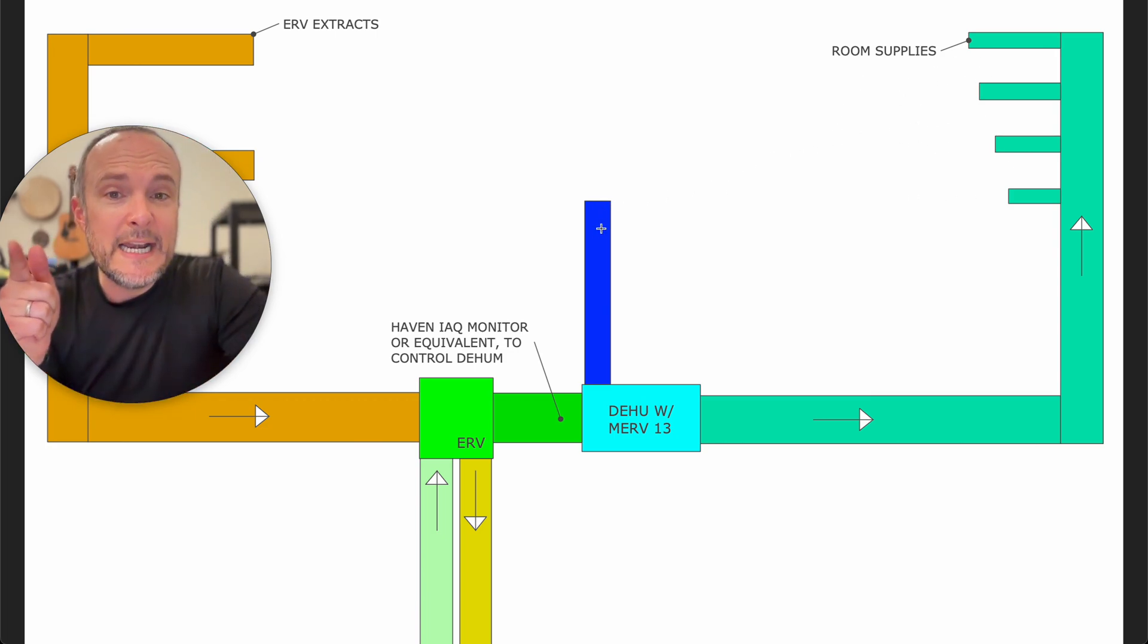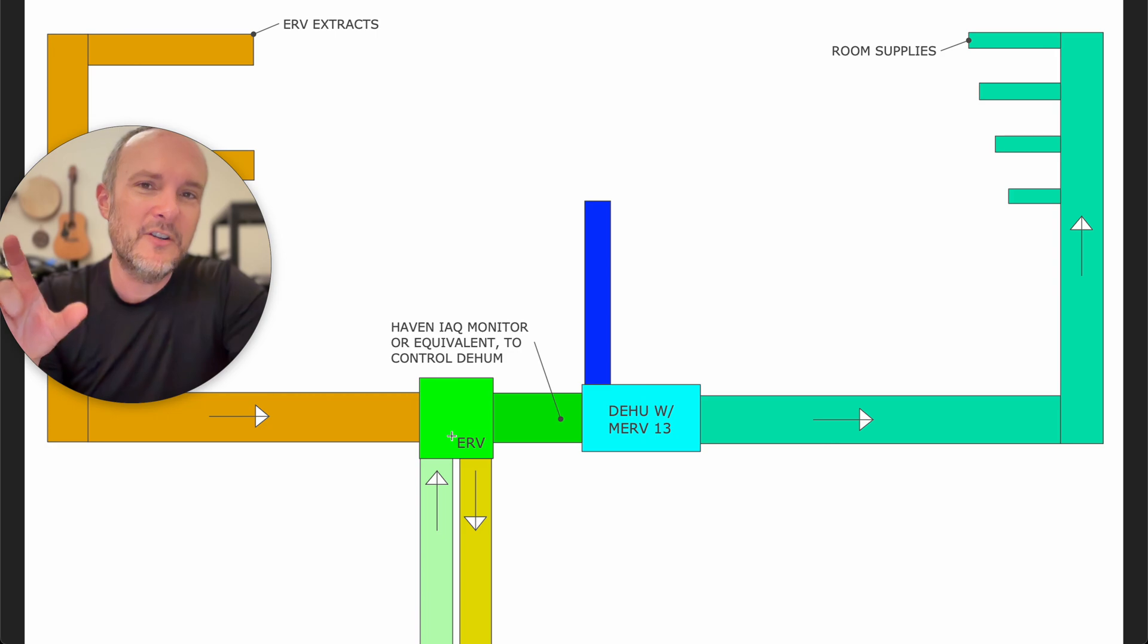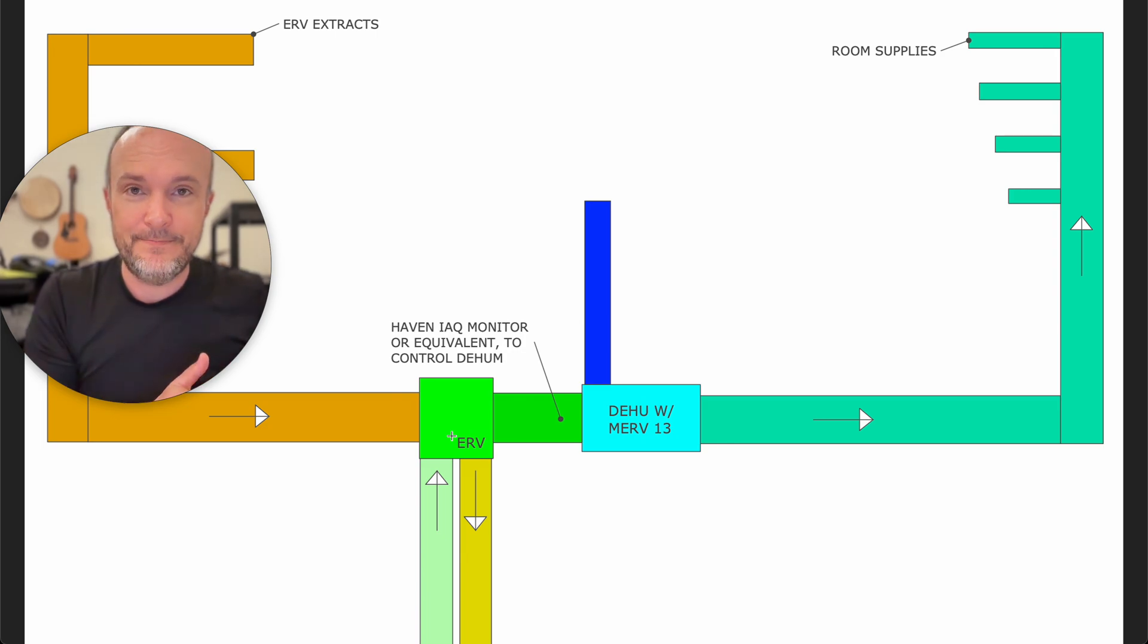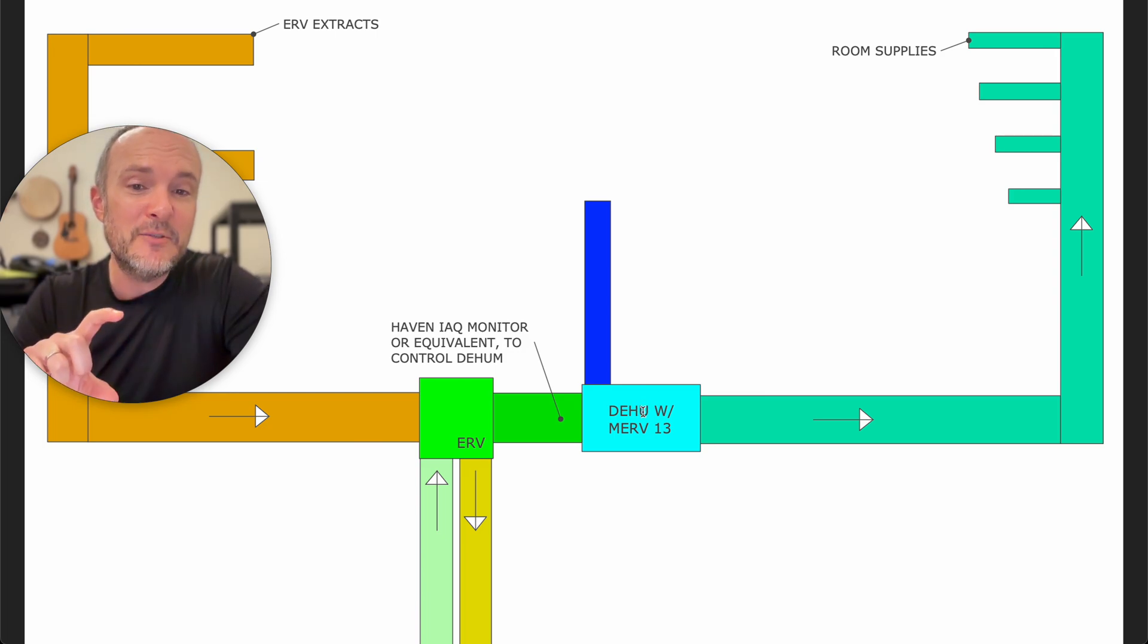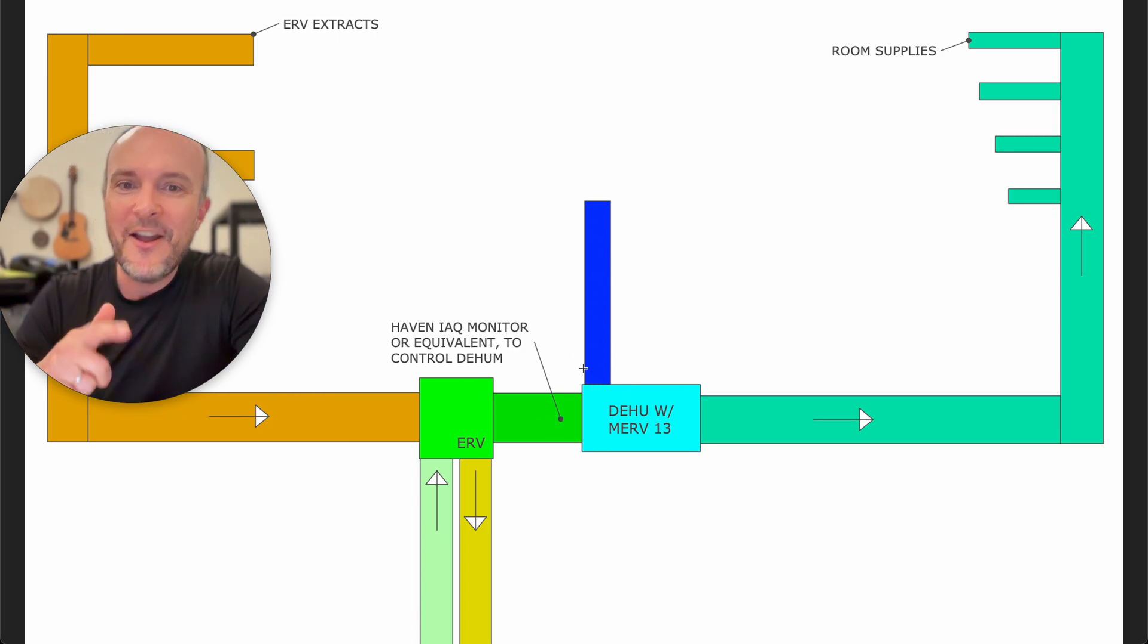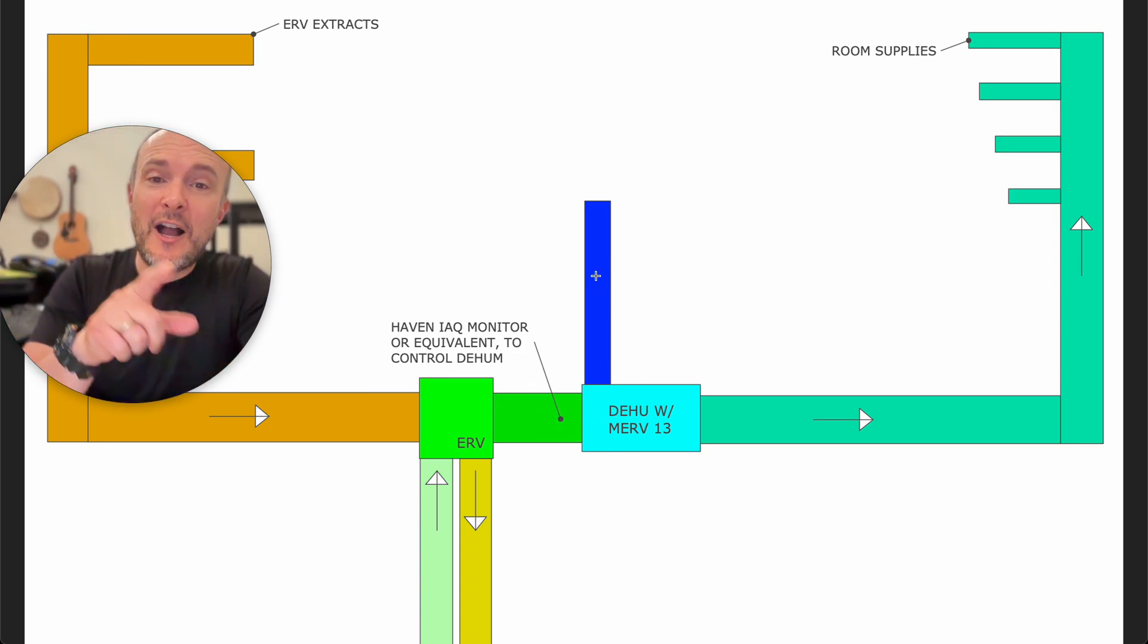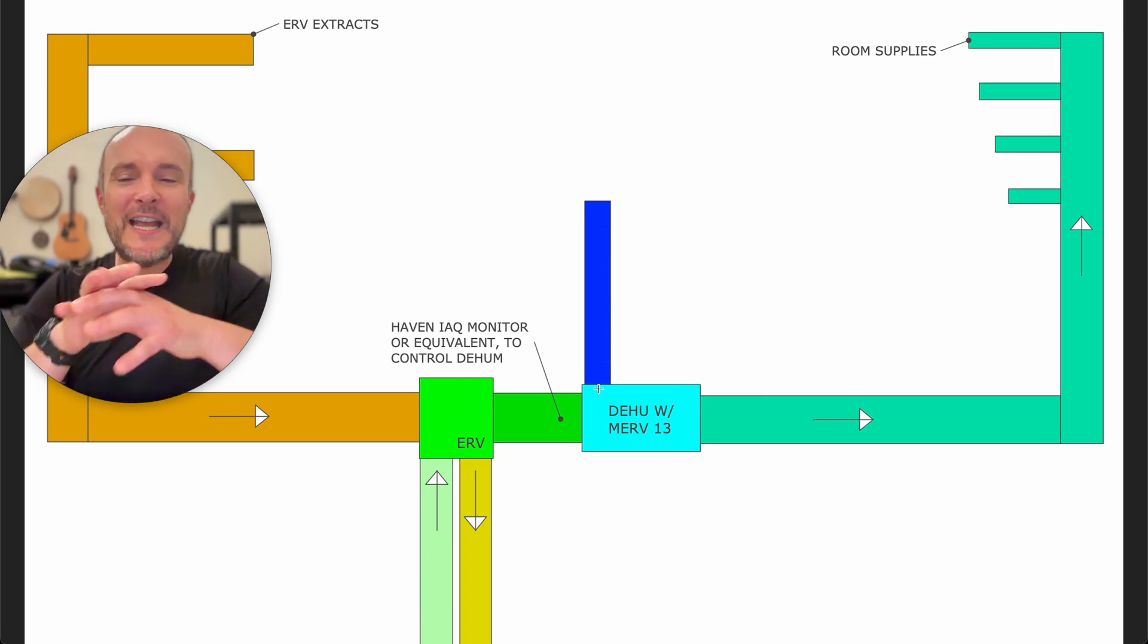That's not entirely true because we're going to need this. This bar right here represents extra air coming into the dehumidifier because an ERV most of the time is going to be 200 CFM or less. In fact, the biggest ERV that I'm normally recommending is 210 CFM. The dehumidifiers run from like 300 CFM up to maybe 500 CFM, so this is a much bigger machine. You can't just feed this machine off of the ERV. We're going to need to have an extra intake on this from the house, whether that intake is after the humidity monitor or before the humidity monitor, and then how big this duct is and how much of the percentage of what this is drying comes from the house—you're still going to be playing catch-up at some point.